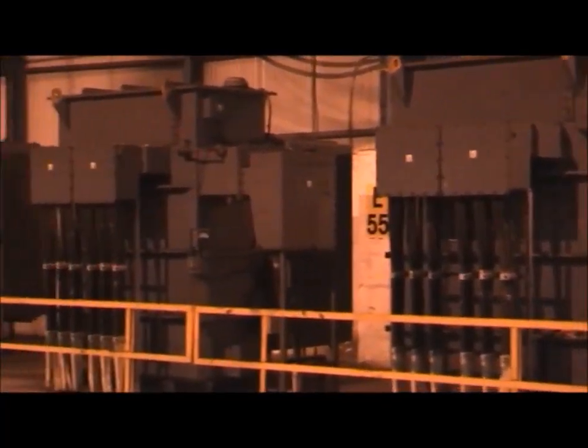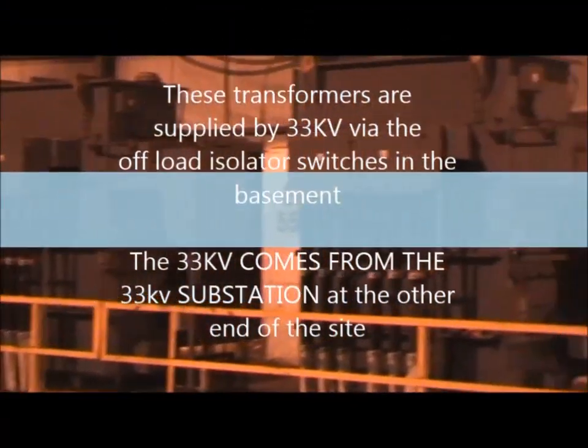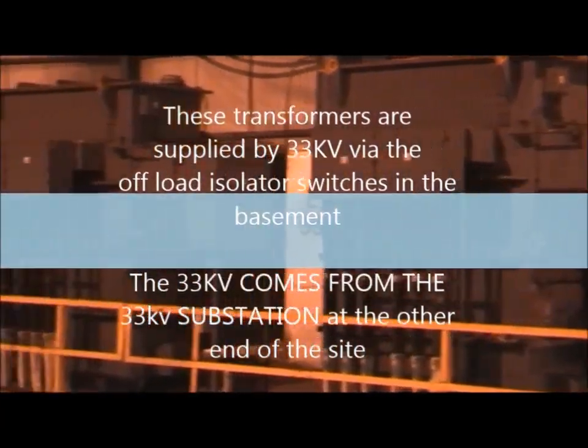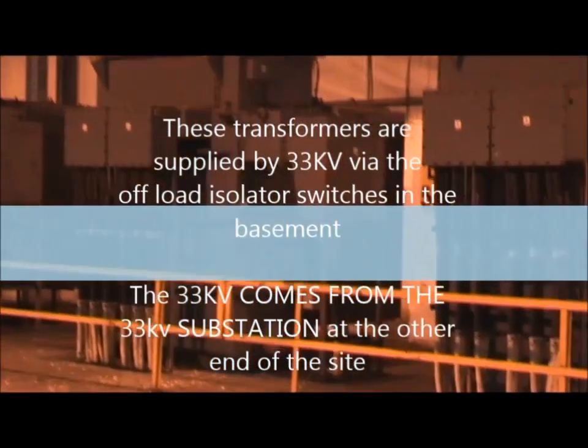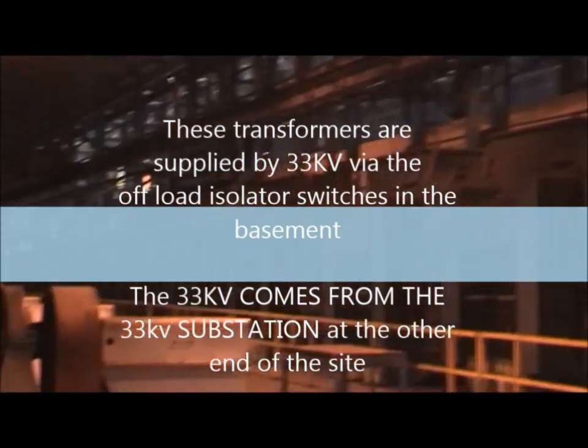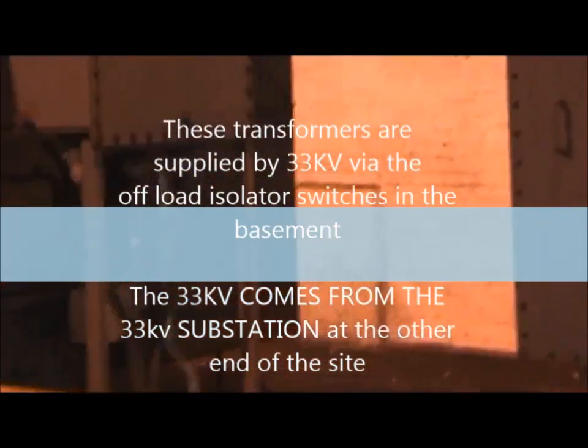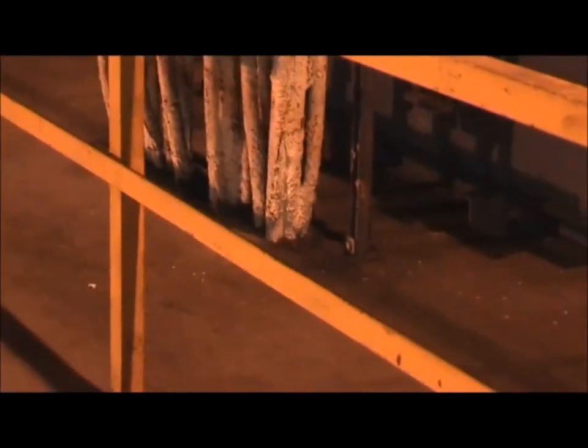And then you have each stand, 2 transformers per stand, one for the top converter and one for the bottom converter, all the way through to the reel. Of course we have 33 kV coming into this box here. The outgoing side, the tails drop down straight onto the bus bars on the converters immediately below.